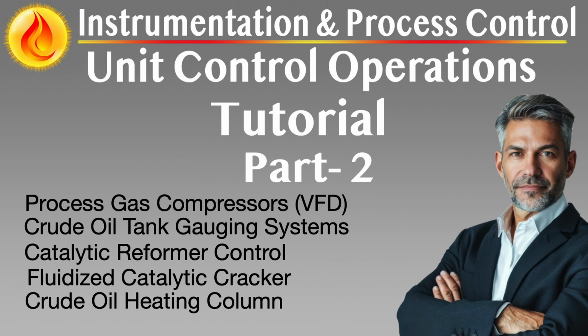operational efficiency. The control of modern semi-regenerative, cyclic, and continuous catalytic reformers, CCR, involves highly integrated systems managing reaction severity, catalyst stability, product quality, energy efficiency, and safety, all within tight environmental and economic constraints. Historically, reformer control was based on fixed ratios and manual tuning of temperature and pressure. Today, control strategies revolve around reaction severity management, where reactor temperatures, hydrogen partial pressure, and space velocity are continuously optimized to maintain octane targets while minimizing coke formation and catalyst deactivation.